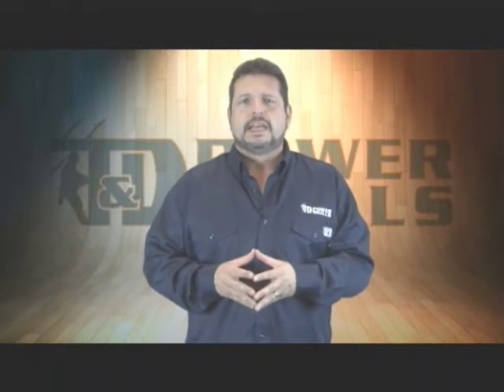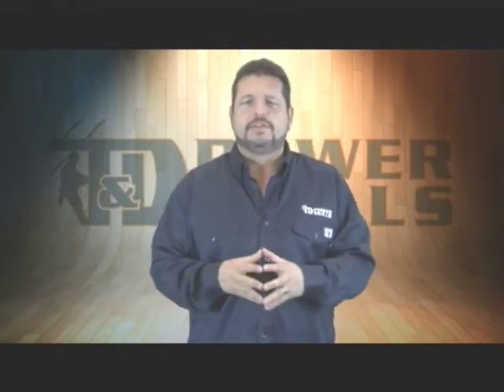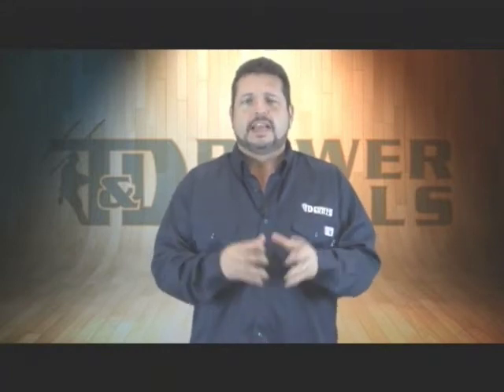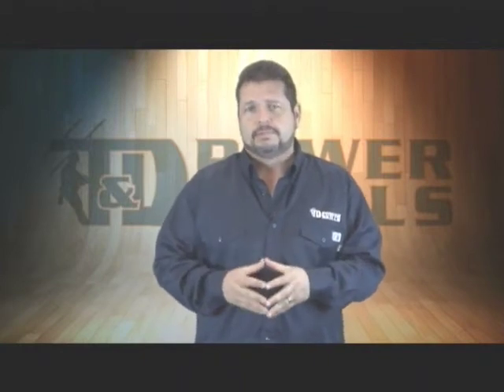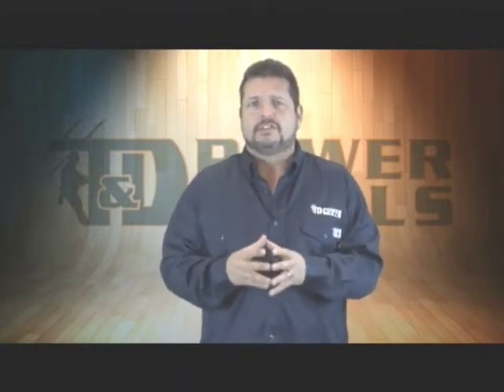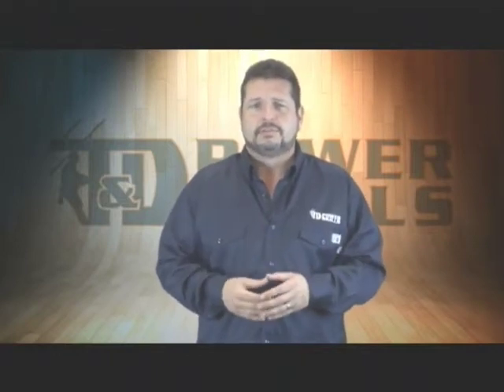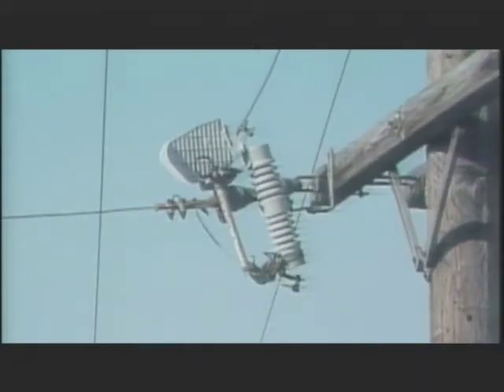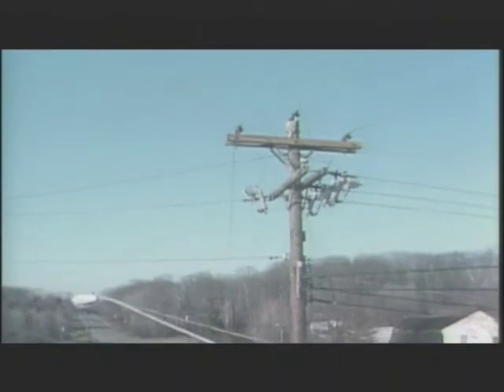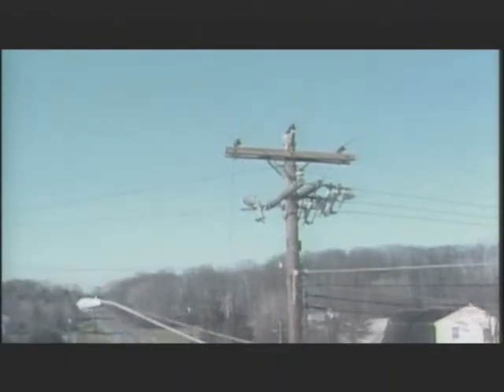This is one type of switch commonly used in overhead distribution. It's called a cutout or sometimes a fused disconnect. Now, cutouts are mainly used as protection devices. They interrupt current flow to equipment that could be damaged in the event of an electrical problem. They can also be used to open or close circuits when equipment has to be taken out of service for maintenance. Some cutouts are connected to poles at points in the line where primary conductors branch off toward specific distribution areas. These points are called junctions.